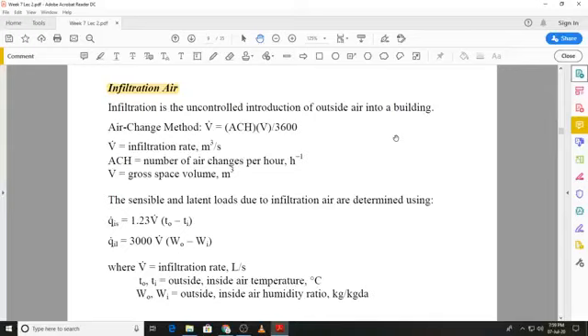The idea of number of air changes is that, for example, if we have a conditioned space whose total volume is 100 cubic meters, and if we measure the amount of infiltration in 1 hour and it comes out to be 50 cubic meters, that means the number of air changes per hour will be 50 by 100, that is 0.5 ACH. That means the ACH value will be 0.5, and to convert that into meter cube per second, you will divide it by 3600.